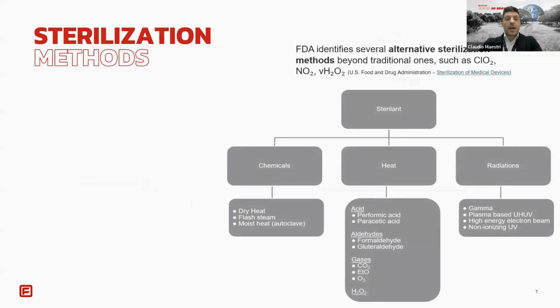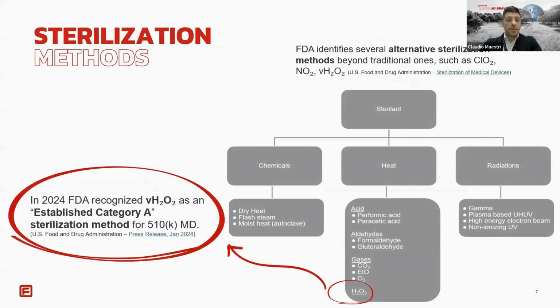Medical devices can be sterilized in several ways, including using moist heat, steam, dry heat, radiation, ethylene oxide gas, vaporized hydrogen peroxide, and other sterilization methods, for example, chlorine dioxide gas, vaporized peracetic acid, and nitrogen dioxide. FDA has announced in January 2024 that it now considers vaporized hydrogen peroxide to be an established method of sterilization for medical devices, recognizing the modality's long history of safety and effectiveness. FDA recognition of H2O2 as a category A sterilization process places H2O2 on par with moist heat, dry heat, and radiation.